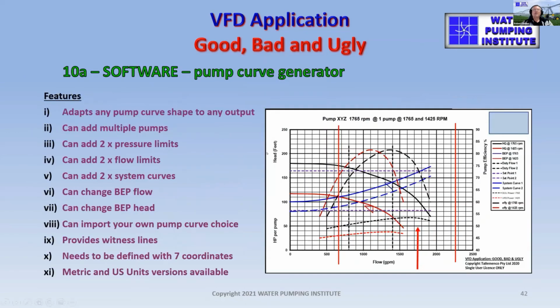So that gets back to, well, how do we ensure that you're going to get value for money when you install a VFD? You really need to go back to the basics: work out what pump performance you have, what the duties are, and use this type of software to run it through the paces. Set your pump to work on this software before you even think about putting a VFD on there. And this particular software, you can add multiple pumps.